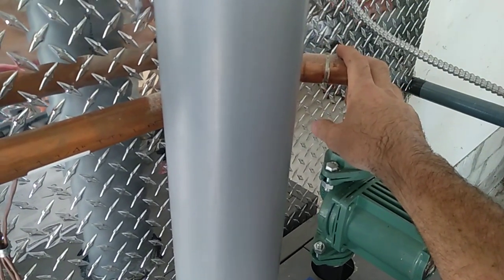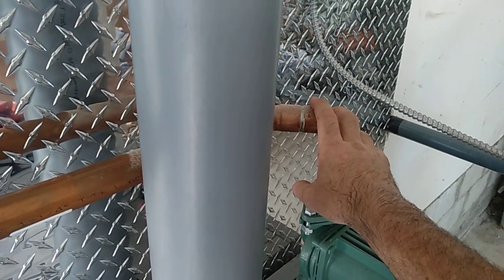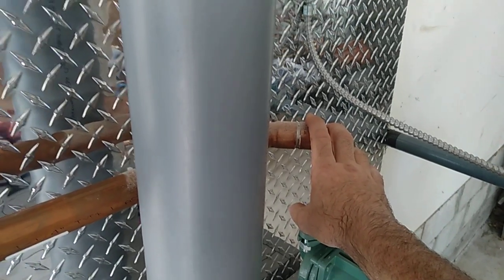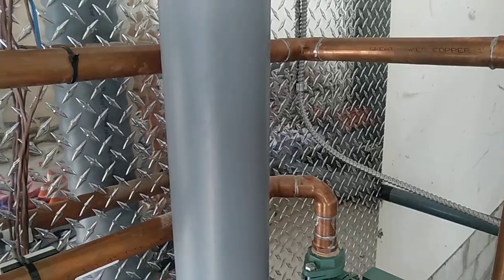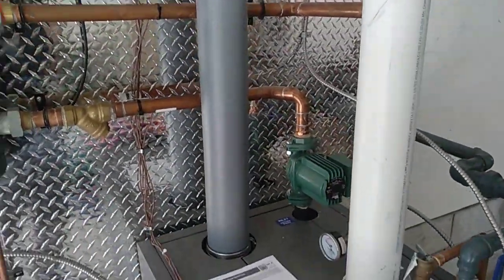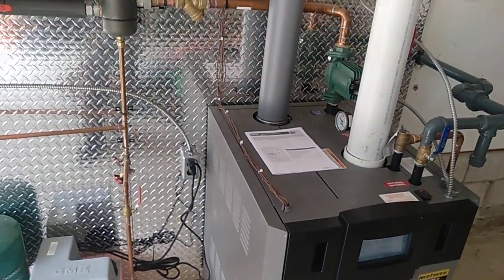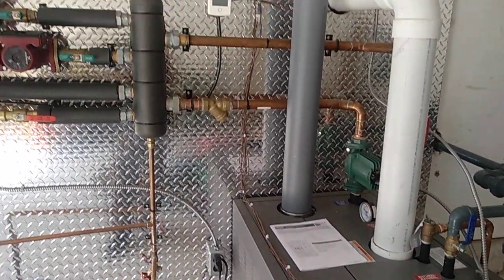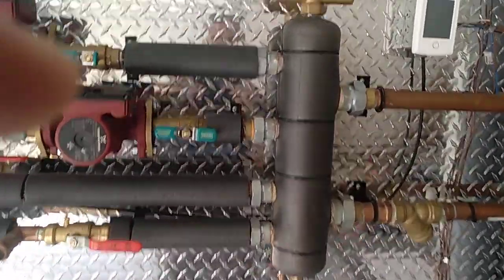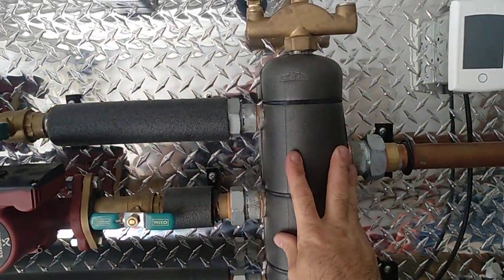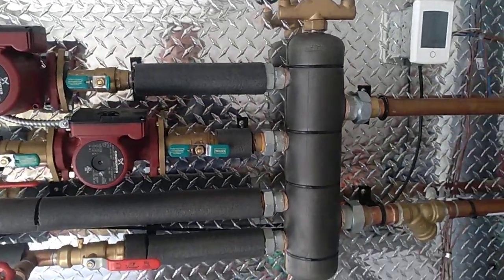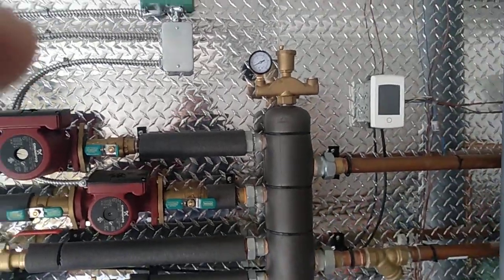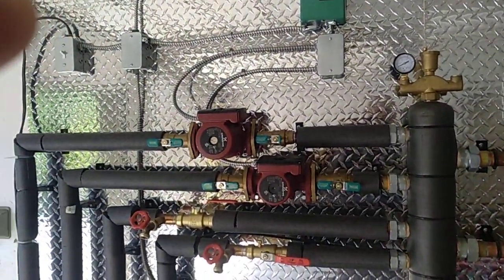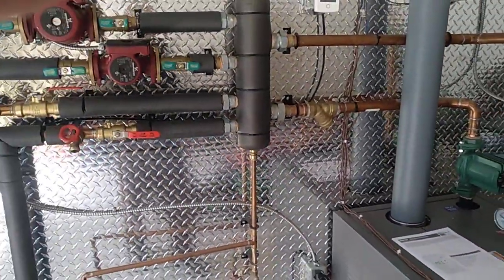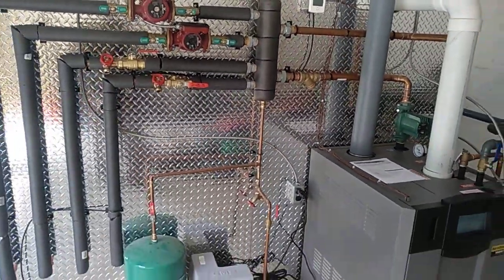So the difference between this pipe and this pipe will not be 170 Fahrenheit, but only, let's say, about 100 or 80 Fahrenheit. So there is a whole lot less expansion and contraction on the two sides of the heat exchanger that's built into this boiler, and it will prolong the life of the boiler tremendously. So this is the reason why we're using the Schuler hydraulic separators. We have them different sizes, 1 out, 2 out, 3 outs, and this protects both the concrete slab as well as the boiler. So everything is working properly, and we just finished this project.